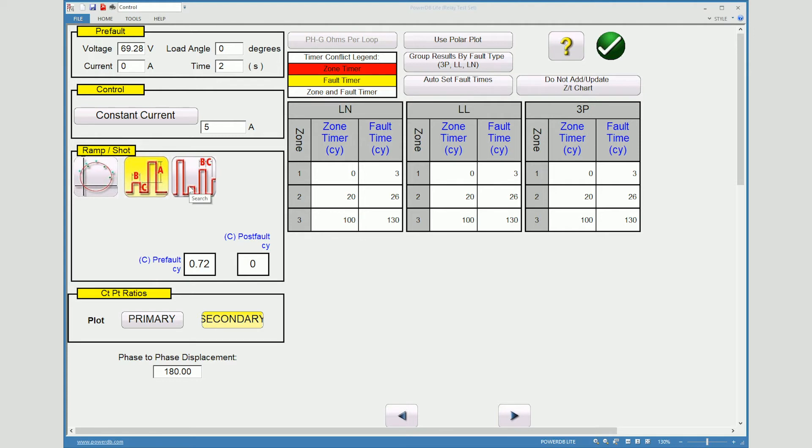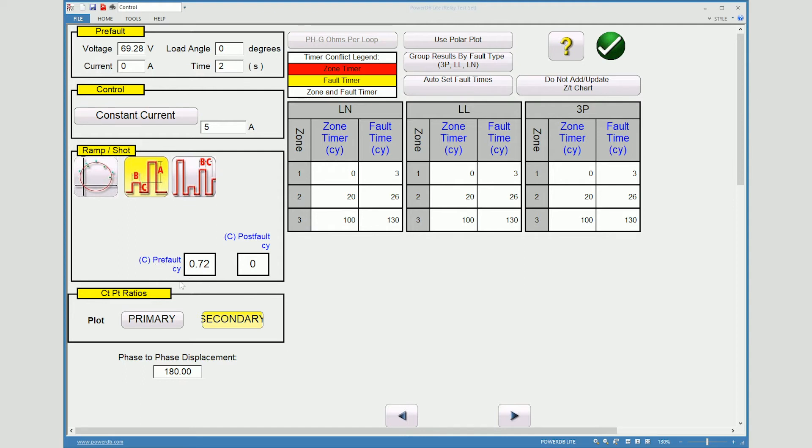Or we can do a binary search and allow it to pulse in the zone, out of the zone, in the zone, out of the zone to fine tune where that point is where it operates and doesn't operate. And then also some type of pre fault cycles will be applied as well during this test.